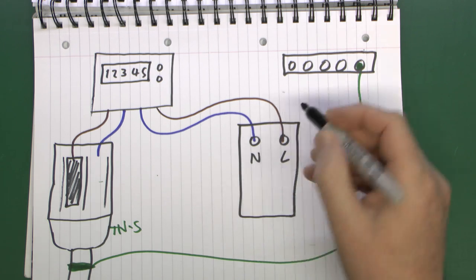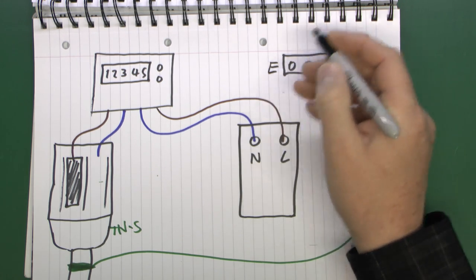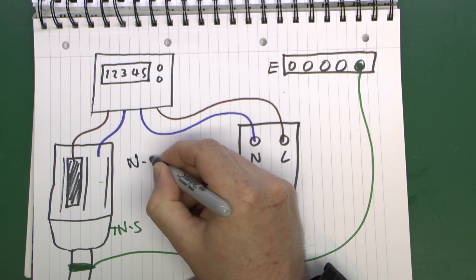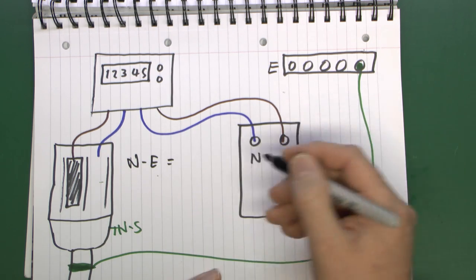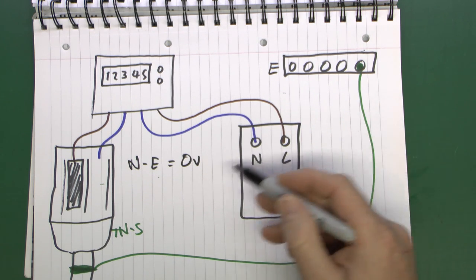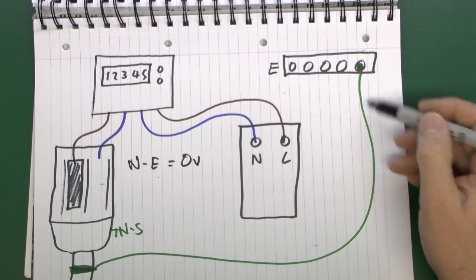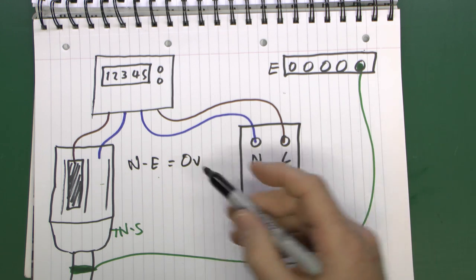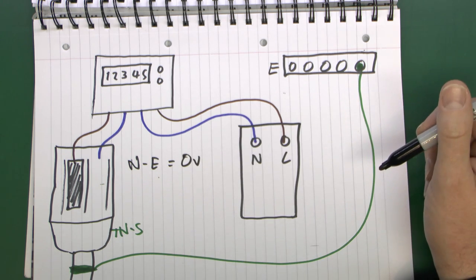So between neutral and the earth connection, you basically should have zero volts or as close to that as practically possible, maybe one volt or something depending on the other circumstances of how the earth is connected, but essentially as close to zero as possible.